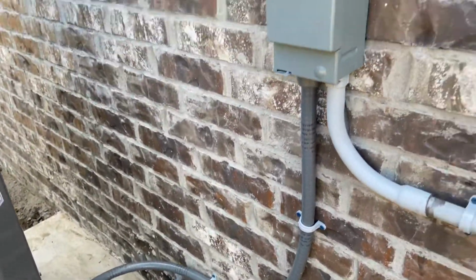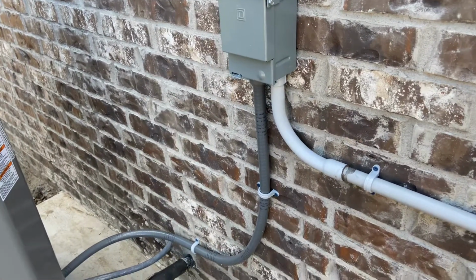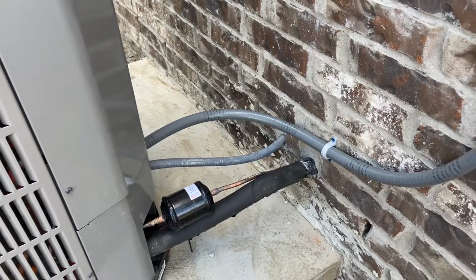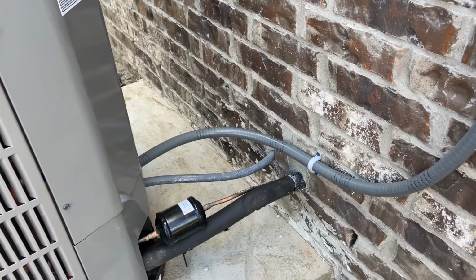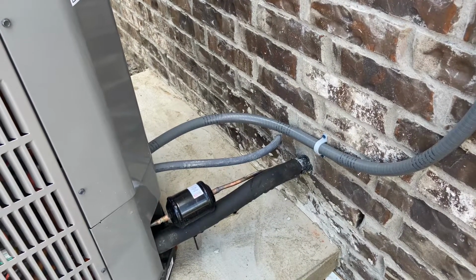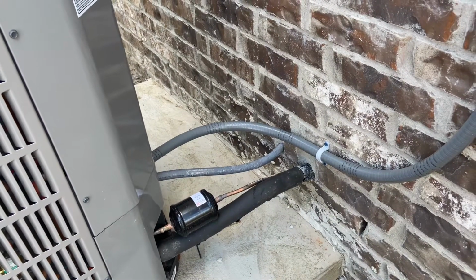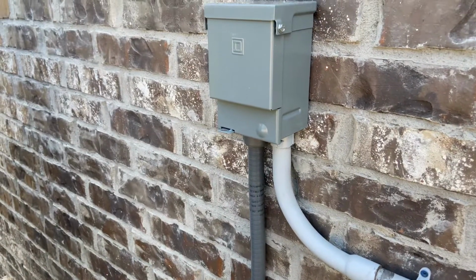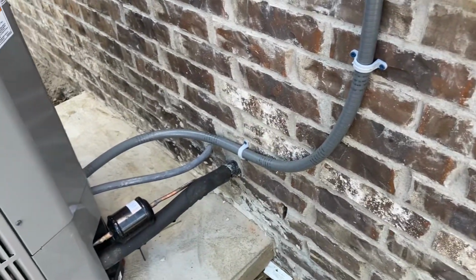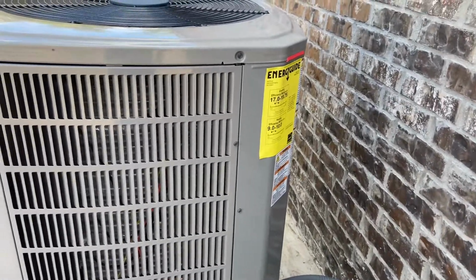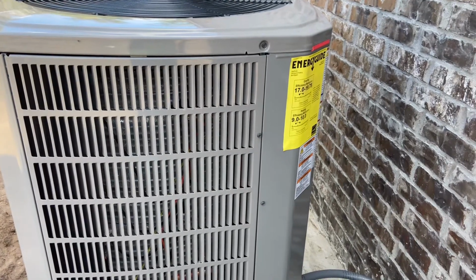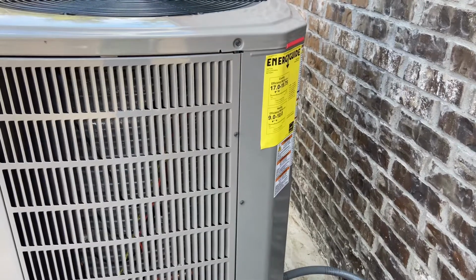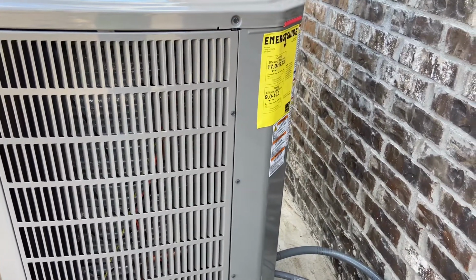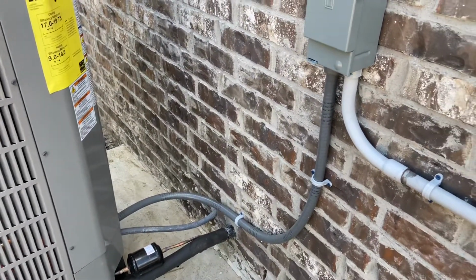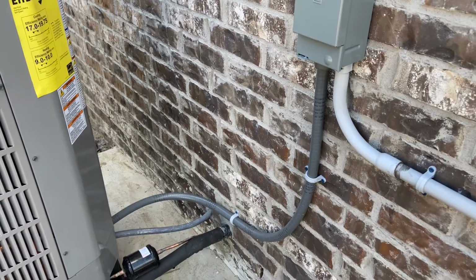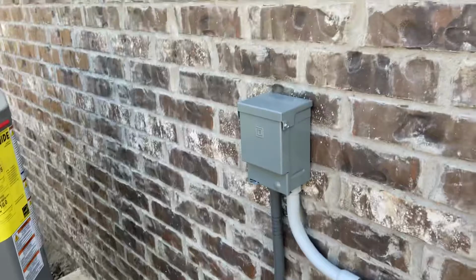What I gave my HVAC guys was this stub, these whips, and this electrical stub out. So that half-inch flex line coming out of the brick, that's the control wires I ran earlier. I just gave them a half-inch flexible liquid-tight conduit. Then for the high voltage, the 220 lines, I mounted the disconnect and gave them another whip. This particular heat pump, the biggest and baddest, runs about 37 amps at load with 50 amps of overcurrent protection. Looking at the tables, 75 degree C column, THHN, that translated to number 8 conductors with a number 10 ground. So that's what I ran, two hots and a ground.